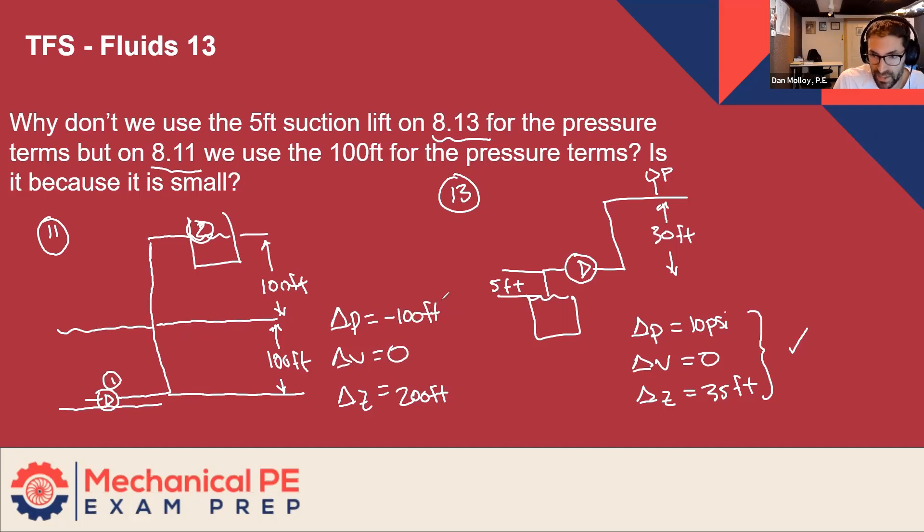So then when you add all this together, the total HA, the total head that needs to be added by the pump is 200 minus a hundred, which is a hundred feet. And that ends up getting put into the power equation. And that's the approach to the solution.